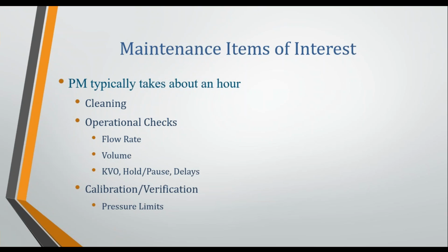Then the other part of your typical PM is you're going to do operational checks. You're going to check the flow rate, you check the volume, you check other functions if the system has it, such as KVO, holds, pauses, delays, a few of the things we talked about like that. And then the calibrations and the verifications, you're going to be checking on pretty much all the contrast injectors, all your pressure limits. Again, all these are done annually.